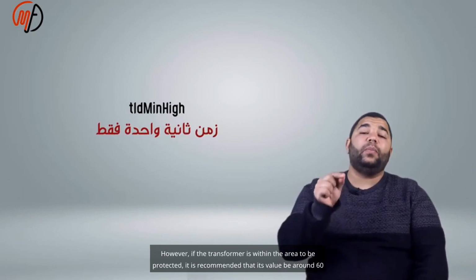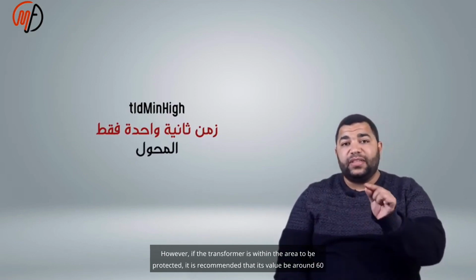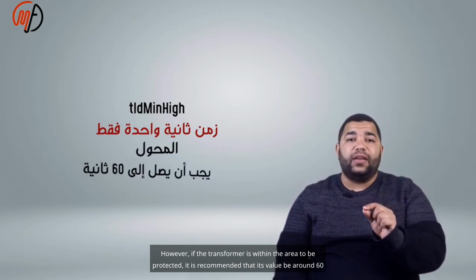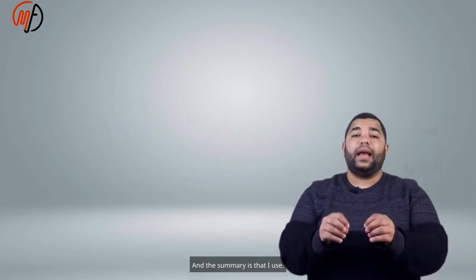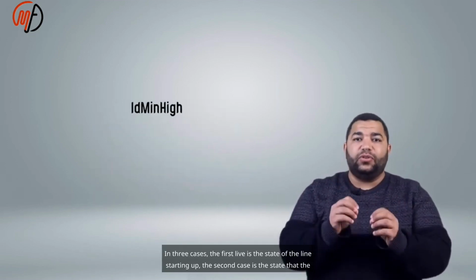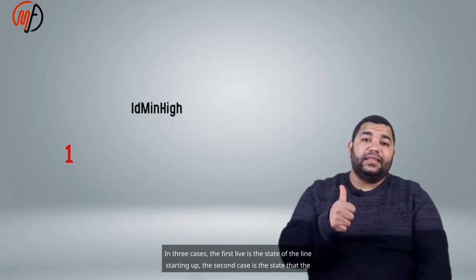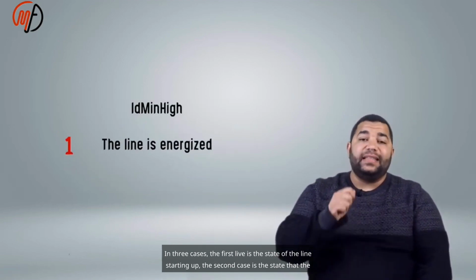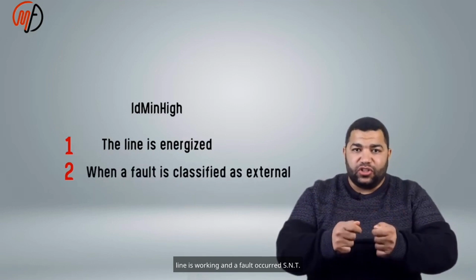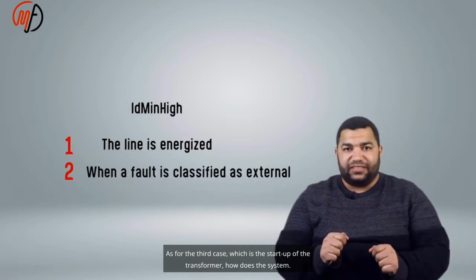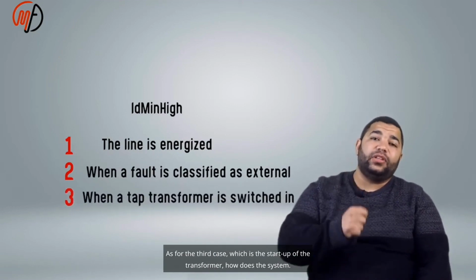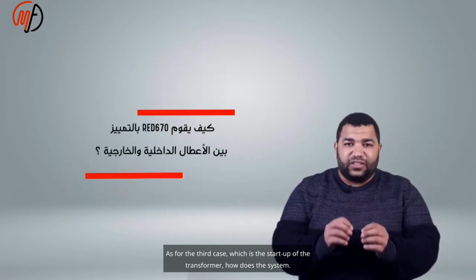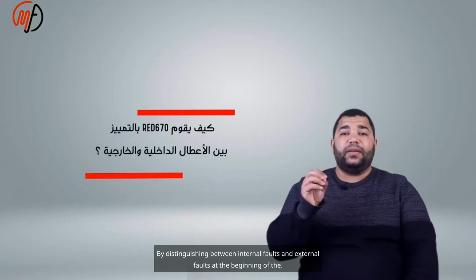However, if the transformer is within the area to be protected, it is recommended that its value be around 60 seconds. And the summary is that I use it in 3 cases. The first is the state of the line starting up. The second case is the state where the line is working and a fault occurred. As for the third case, it is the startup of the transformer.